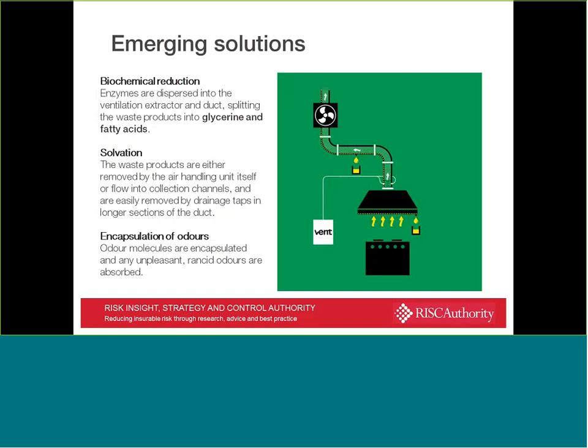Emerging solutions, which I just thought I'd touch on before I shut up. We've had a presentation from this organisation. They produce a product called Vent, which uses a biological agent which is sprayed at regular frequency into the extract ductwork, which is understood to break down the grease and oils that may be deposited inside into glycerin and fatty acids. It then suggests that the waste products are either removed from the air handling unit itself or flow into collection channels. Now, the presentation that we saw and the individual involved in the presentation wasn't really clear on how this residue was taken away, and at the moment we've taken discussions with them no further. Clearly we need to keep RC44 up to date, and it will be going through a review process, as I mentioned earlier, and we'd need to comment on these kinds of systems as a result of that, but at the moment we've said no more to them.